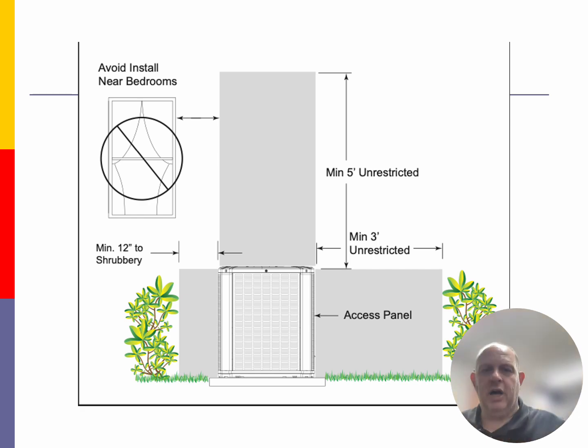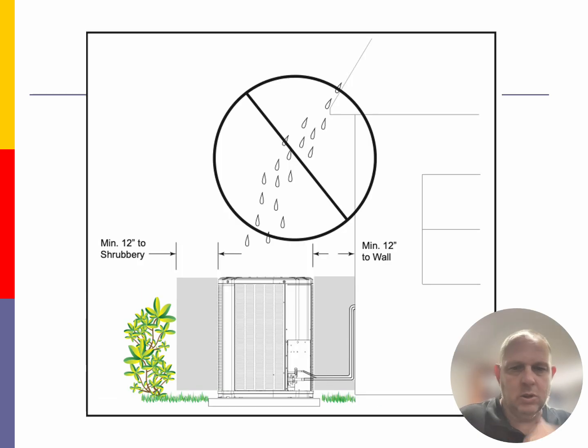Another area that we want to watch for is runoff from the roof onto the condensing unit itself. We want to try to avoid that rain. Now, it's just going to create a water issue. I know it's outside. It's just going to create some sort of condensation issue on the inside, moisture with the boards, the contactors, and other pieces of equipment out there.